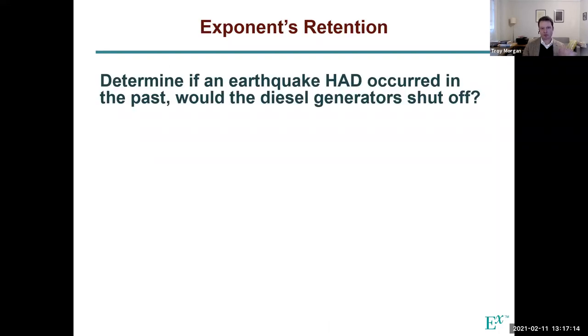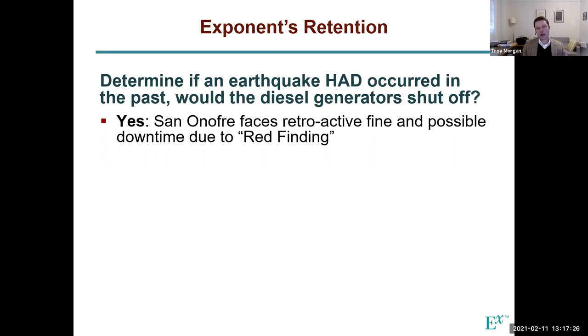But our mission in this case was basically: go back and figure out if an earthquake had occurred in the past, would the generator have shut off accidentally? If yes, that would be a problem, because the plant itself was already having some regulatory problems due to the steam generators, which is a separate talk entirely. But finding a non-compliance issue with this vibration monitor...